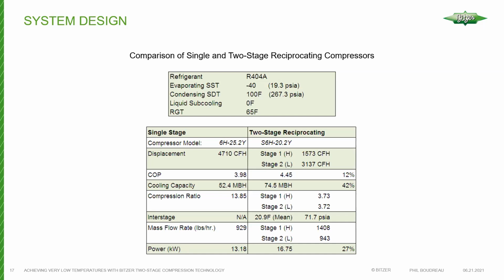And in this case, we have 4,710 cubic feet per hour, and we're operating 404 at -40 and 100 degrees, so minus 40 saturated suction temperature, 100 degree Fahrenheit saturated discharge temp. And then we've got no subcooling in this case, just for an example, and a 65 degree return gas. So displacements, when you add up the two stages of the S6H-20.2 two-stage compressor, they add up to 4,710. So we're comparing like for like displacements here.